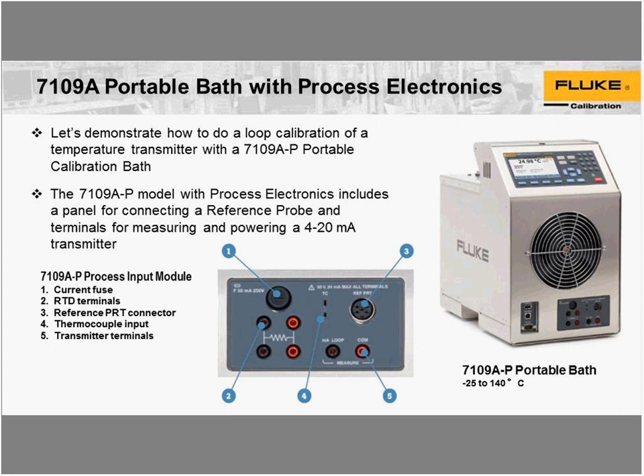The -P in the 7109A-P stands for process electronics. So the baths come in two main configurations: without the process electronics board, or with the process electronics. Process electronics has 8 terminals. This is for measuring a PRT under test. It has a reference PRT input for, of course, measuring the reference PRT.